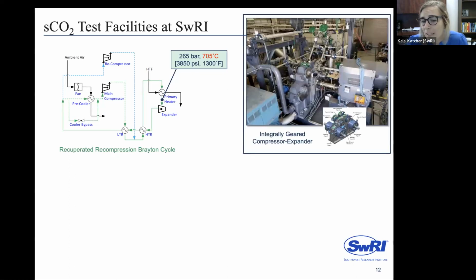The first is an integrally geared compressor expander. Here we actually have compressor stages and expander stages built on the same machine with a single bull gear. On the full build, this is a 10 megawatt frame. You would be directly coupled to a generator, an 1800 RPM generator, and outputting from a single frame with a very small footprint compared to a steam system or an ORC system.